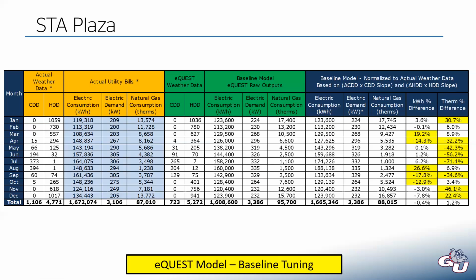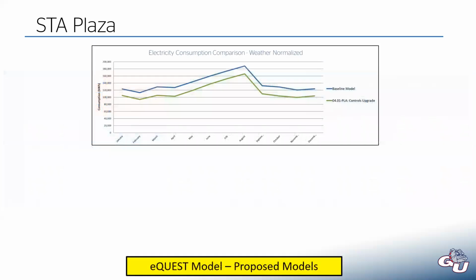From here, I create a new version of the model where now we get to play with, well, what are we going to be doing? What are the changes we're going to make? So we would go into the model and implement those controls related changes. So we would implement demand control ventilation. We would put in consistent set points and our scheduling and anything else we're doing. And then we run the simulation again. And that gives us this delta. Our blue line is our baseline model. And then our green line for our controls upgrade version of the model, you can see there's a pretty consistent delta pretty much year round. And that would be our savings.